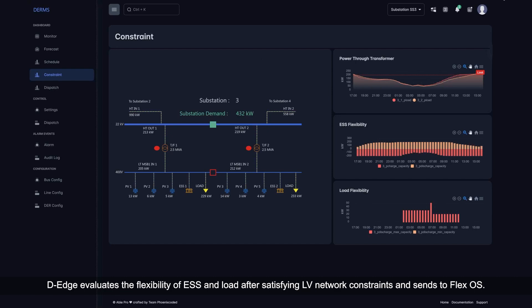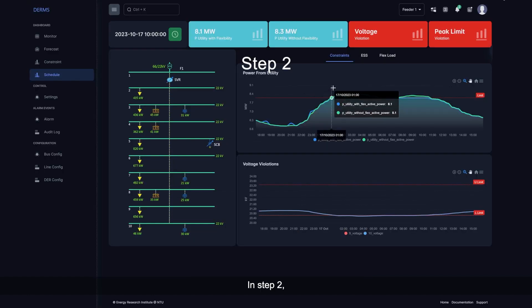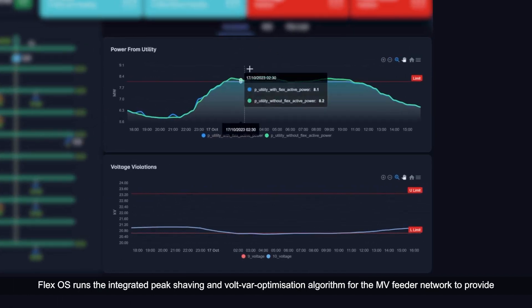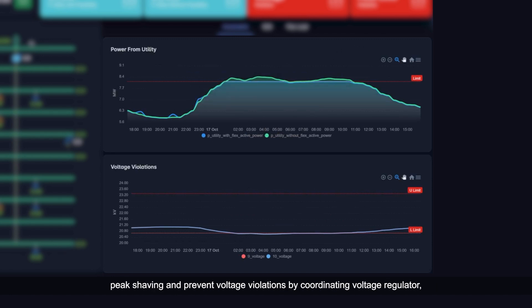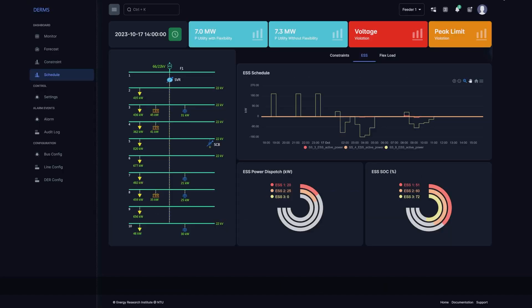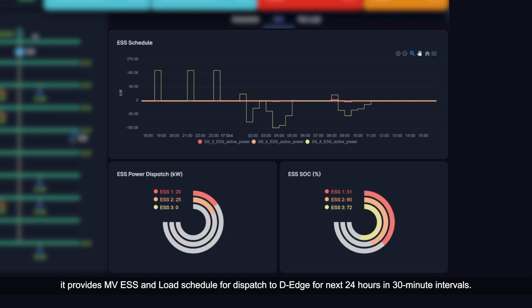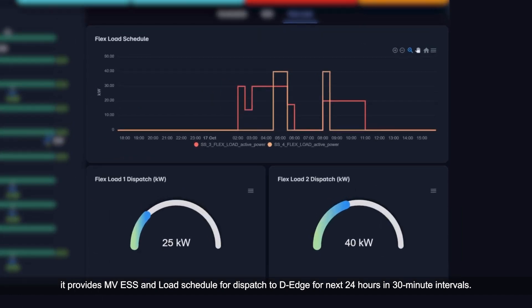In step one, D-Edge evaluates the flexibility of ESS and load after satisfying LV network constraints and sends it to FlexOS. In step two, FlexOS runs the integrated peak shaving and volt-var optimization algorithm for the MV feeder network to provide peak shaving and prevent voltage violations by coordinating the voltage regulator, CAP bank, and flexibility from D-Edge. It then provides MV ESS and load schedule for dispatch to D-Edge for the next 24 hours at 30-minute intervals.